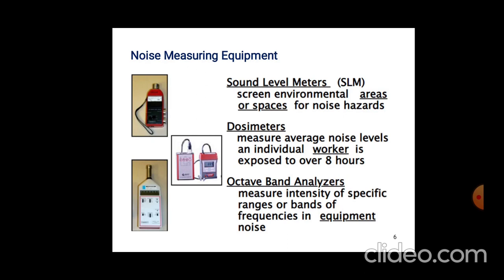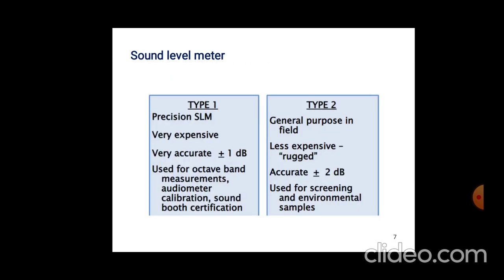The Sound Level Meter has two types: Type 1 and Type 2. Type 1 is used where precision is required and is very expensive, with accuracy of plus or minus one decibel. Type 2 is less expensive, with accuracy of plus or minus two decibels, and is used for general purpose field measurements. Type 1 is used for octave band measurement, audiometer calibrations, and sound booth certifications, while Type 2 is used for screening and environmental sampling.